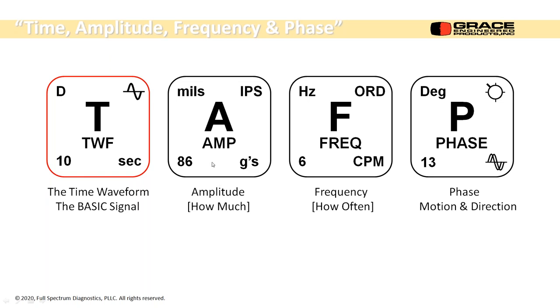Okay. So this is our first wave. This is how our online transducers work. They'll be collecting data and doing analysis until an alarm is exceeded. So it's our first warning that something has changed and something's impending failure. We're going to have to figure out what it is before it fails.